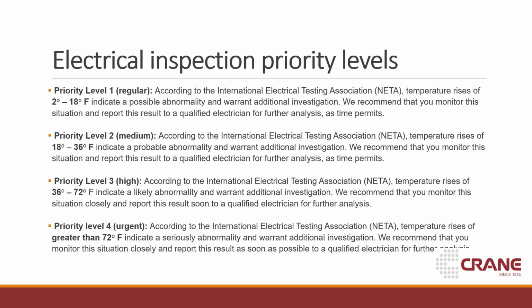We have 4 different priority levels. What we do is take the ambient temperature, so let's say it's 72 degrees in here, and then we apply different priority levels. Obviously, the hotter that panel or breaker is, the higher priority level it is, meaning something you have to take care of sooner rather than later. We start at the lowest priority level, 2 to 18 degrees above ambient, which is an area where you just keep an eye on it.